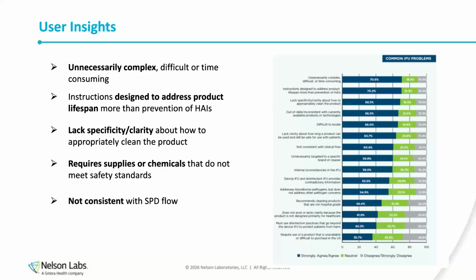So when you're writing your IFU for reprocessing, when you're thinking about the design of your device and you're keeping the user in mind, you have to consider if your device is something that's going to take 30, 45 minutes to reprocess, that's going to be pretty disruptive to the SPD who's getting in cases and cases of reusable instruments that they have to process quickly. It also is going to hinder them if they have to question what's being asked of them, or if they can't really understand what is expected. So again, with the human factors testing, you get all of those insights before you put that IFU on the market.